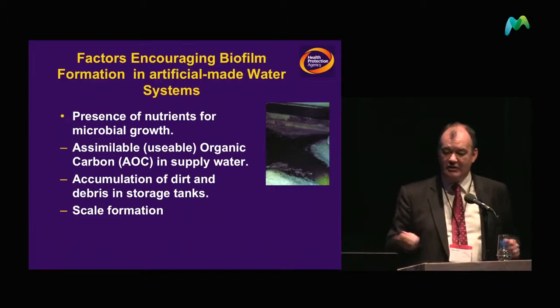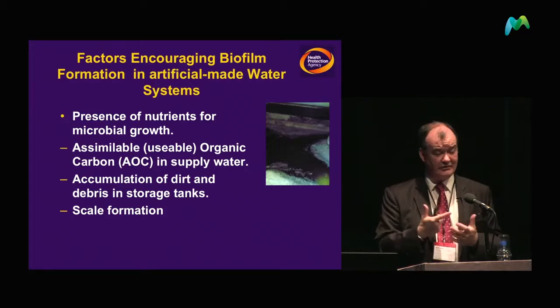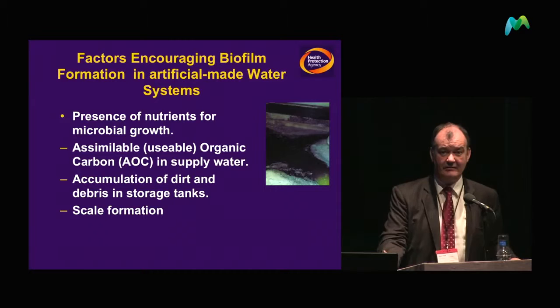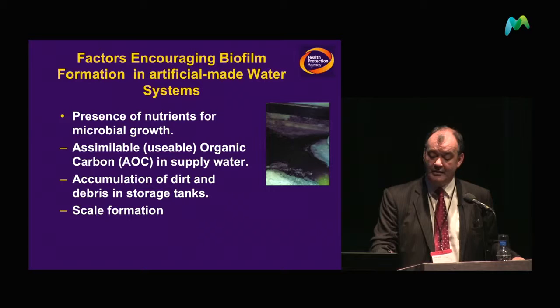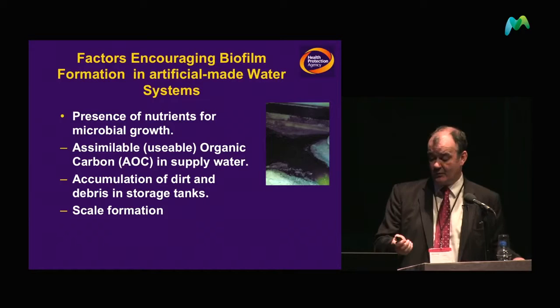In terms of what encourages a biofilm, there are a variety of things: organic carbon, sediment, dirt, debris — but most important is scale formation. Scale formation is a particular issue in the south of England and some parts of the country where the furring in the pipe provides an ideal opportunity for biofilm to develop.